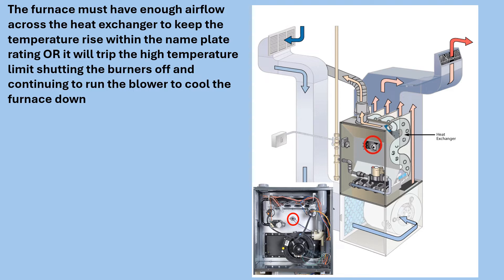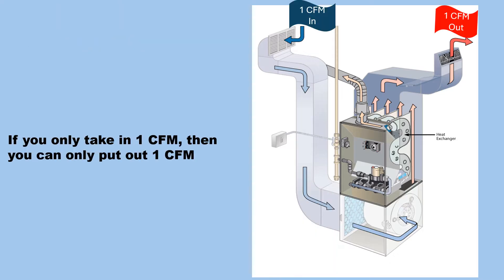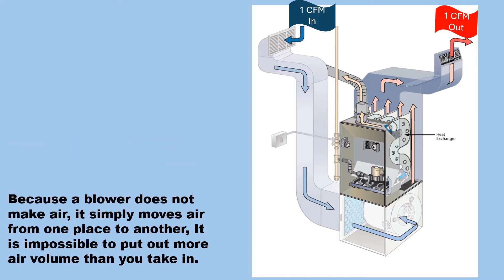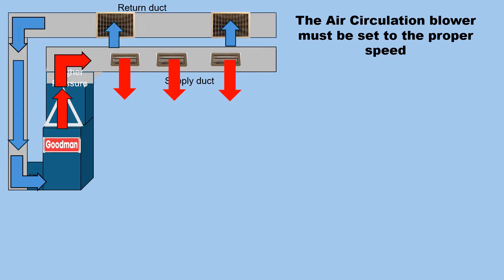The furnace must have enough airflow across the heat exchanger to keep the temperature rise within the nameplate rating, or it will trip the high temperature limit, shutting the burners off and continuing to run the blower to cool the furnace down. If you only take in one CFM, then you can only put out one CFM, because a blower does not make air — it simply moves air from one place to another. It is impossible to put out more air volume than you take in. The air circulation blower must be set to the proper speed.